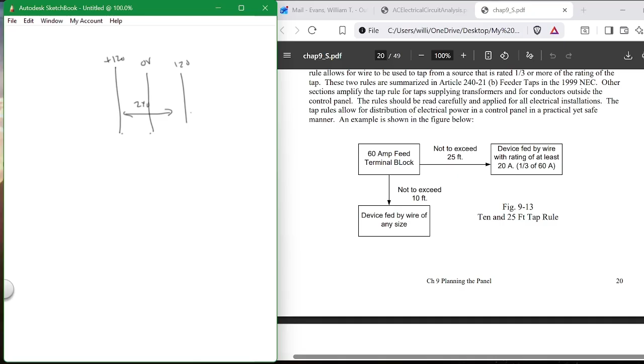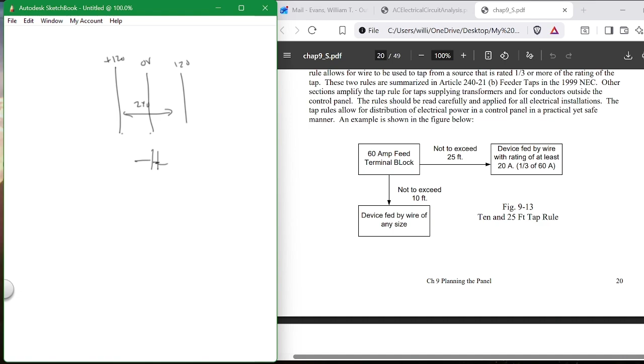Another thing that you're going to run into is that of control voltage. In a house, you have three wires. You have a 0 volts, and you have a plus 120, you have a plus 120, and these are 180 out of phase. There's 240 volts between them. Now, you would never put that in a control panel. Why? Because what will an electrician do if he's in the middle of trying to fix a circuit? If your circuit is off of this side, he might pick this one instead of this one, okay? So if you have 240 in your panel, he might pick the opposite side. And if he does, and the relay contact closes, it will weld, those terminals will actually weld together. So you want to not have 240 in your control panel. You want to have 110. You want to have a lot of circuits of 110, but you do not want to have household in a control panel, all right?